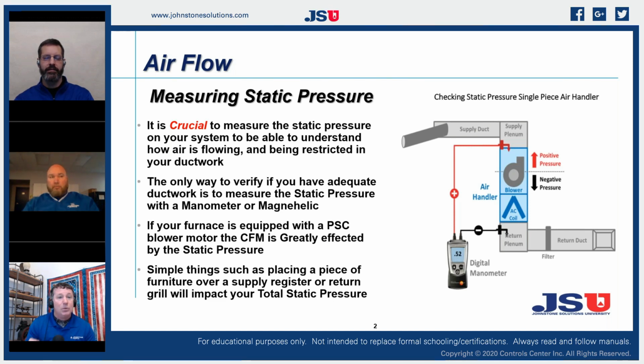So if you have a 1-inch filter in that cabinet, you're not getting the correct static pressure for that blower motor. What was happening is that 1-inch filter was plugged solid, and we had a 1.2-inch total static pressure when we included the pressure drop across the filter, which is more than sufficient to cause that module on the back of that ECM motor to overtemp and throw a B3 fault code for over temperature power limiting. So understanding the placement of that filter in an air handler is critical.